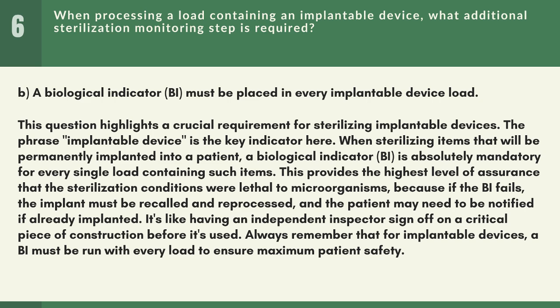This provides the highest level of assurance that the sterilization conditions were lethal to microorganisms, because if the BI fails, the implant must be recalled and reprocessed, and the patient may need to be notified if already implanted. It's like having an independent inspector sign off on a critical piece of construction before it's used. Always remember that for implantable devices, a BI must be run with every load to ensure maximum patient safety.